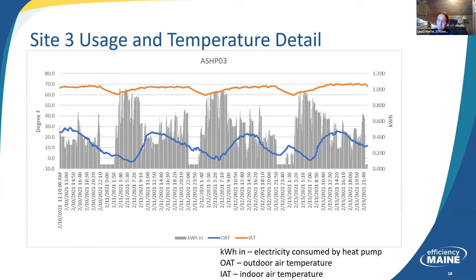Okay, so this is some meter data. Actual usage. This is a home in Gardner, Maine, which is kind of right in the middle of the state. So not the coldest, it's not Caribou, but still pretty darn cold. This was some metering done in February. You can see the blue line is the outdoor temperature. Every night it gets cold, it starts to warm up the next day, and then it gets cold again. The red is the indoor temperature. You can see that it mostly stays steady, but there's some dips. I'll talk about those dips in a moment. And then the gray bars there are the electricity use.